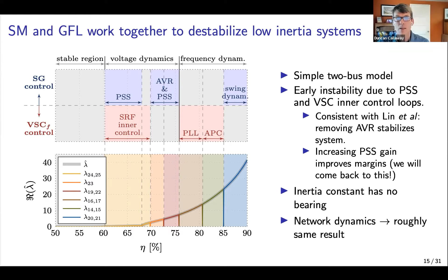Now let's talk about what happens if we add a synchronous machine, a grid-forming converter, remember these are the ones that can form their own grid by regulating voltage and frequency themselves. In this case the system is more stable, but ultimately the same factors destabilize it. Specifically, it's the inner control loops on the grid-forming converter interacting with the power system stabilizer that cause that first crossing over into the right half plane for the largest eigenvalue.